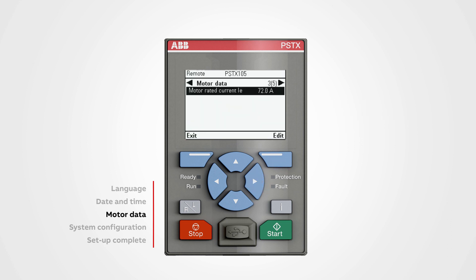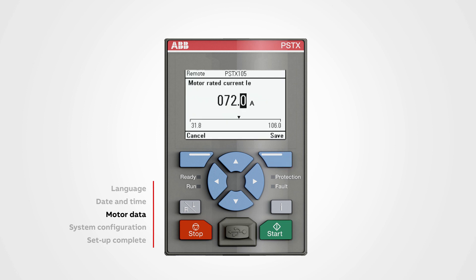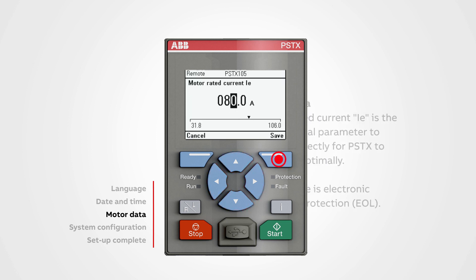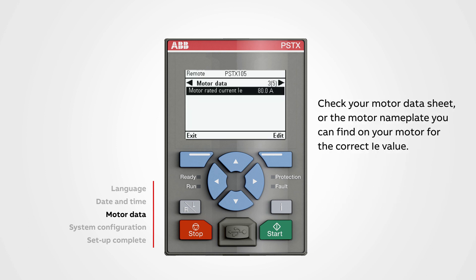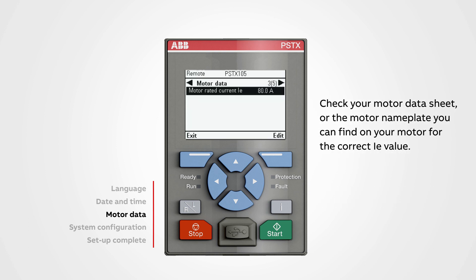Motor Data: Push Edit to change the Motor Rated Current (IE). Use the Navigation Keys to change the value and push Save. Motor Rated Current (IE) is the most critical parameter to set up correctly for PSTX to function optimally. An example is the Electronic Overload Protection (EOL). Check your Motor Data Sheet or the Motor Nameplate on your motor for the correct IE value.